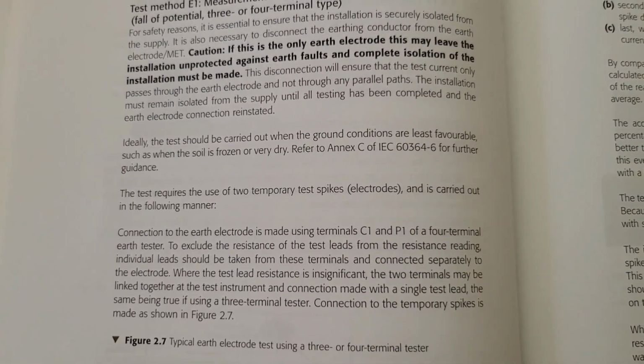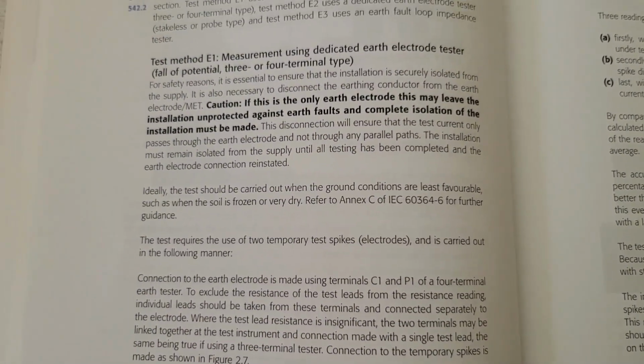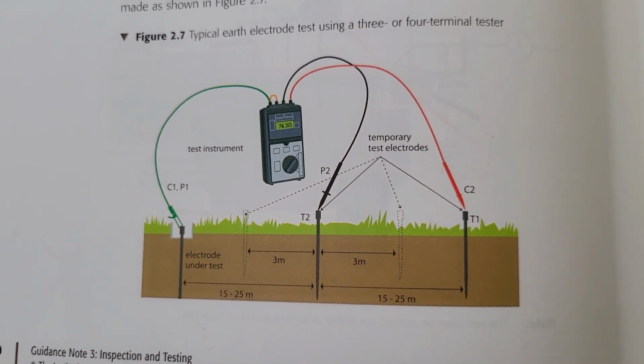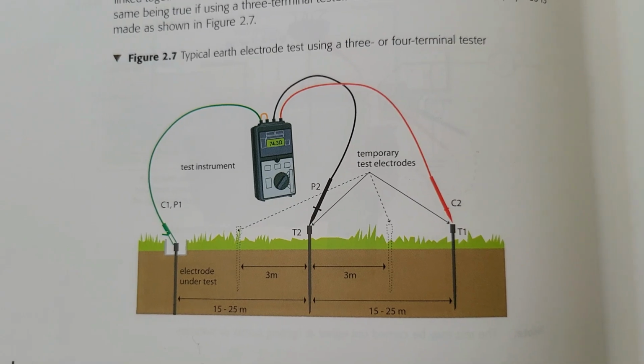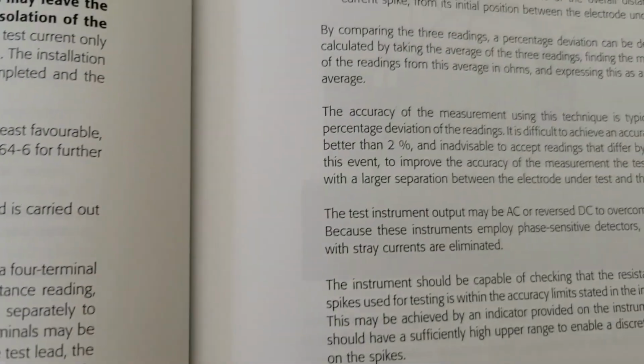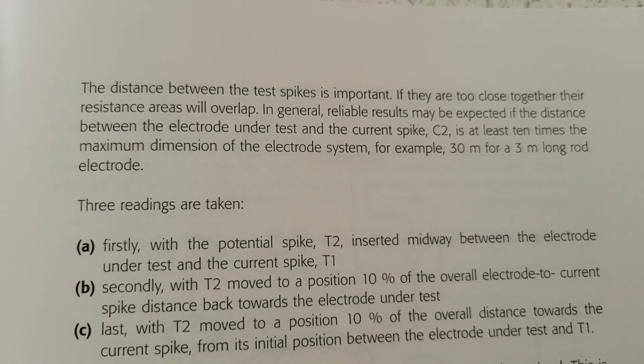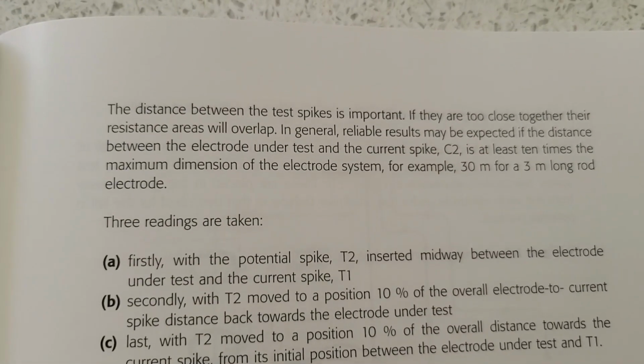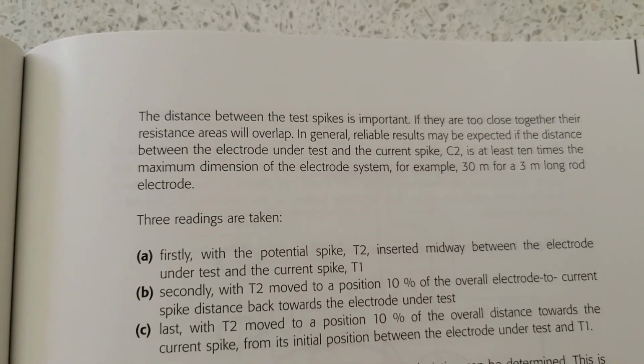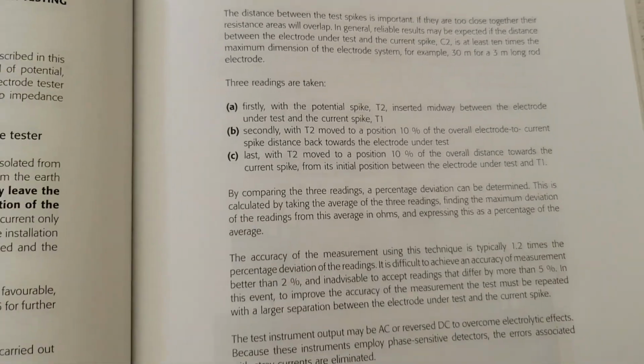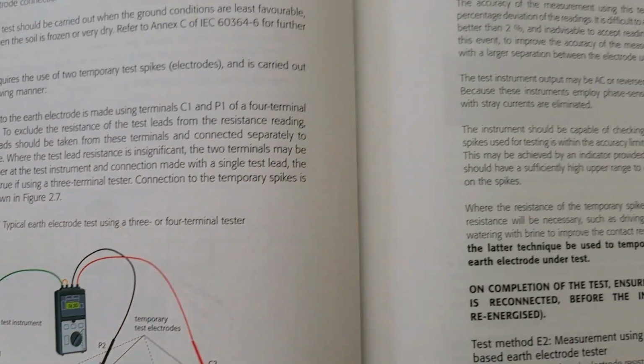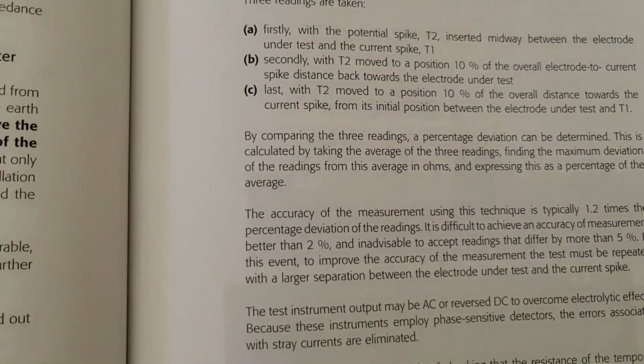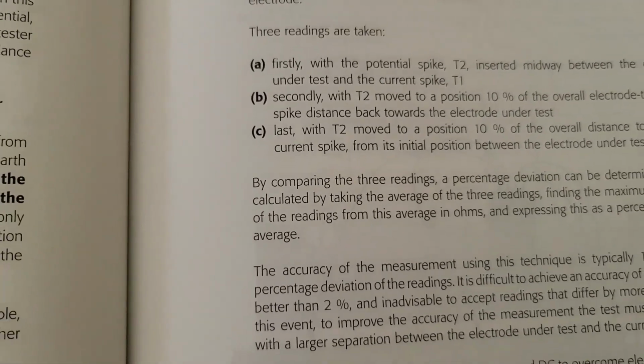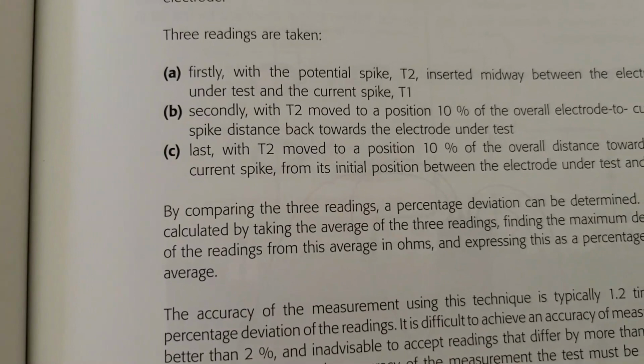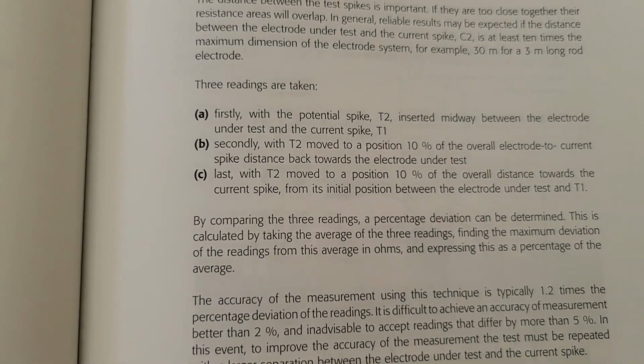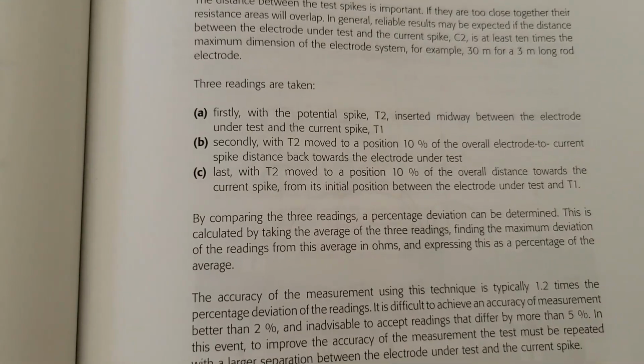It explains about test method E1, which is the measurement down here, where you can see you've got your 2 probes out into the mass of earth and then your earth electrode. And as we said before, as it says up here, you need to be 10 times the maximum dimension of the electrode system. So if you've got a 3 meter long rod, 30 meter distance between your spikes. But as I said on mine, we've got 1.2 meter rod, so those distances drop. It then goes on to talk to you about the measurements that you take, moving the T2, which is the middle spike, by 10%, as we said. And that's to try and give a variation in the measurements.